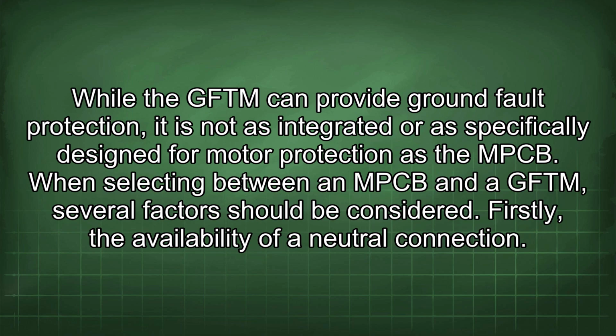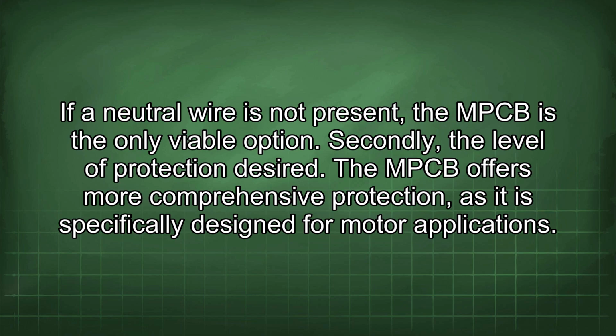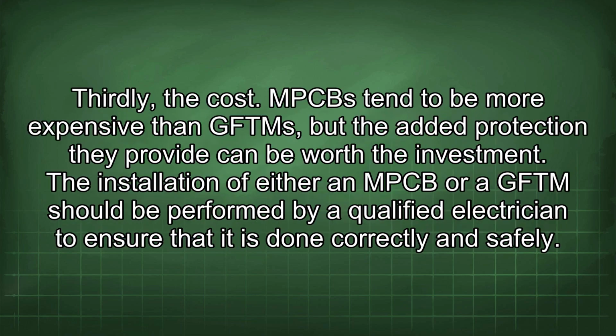When selecting between an MPCB and a GFTM, several factors should be considered. Firstly, the availability of a neutral connection. If a neutral wire is not present, the MPCB is the only viable option. Secondly, the level of protection desired. The MPCB offers more comprehensive protection, as it is specifically designed for motor applications. Thirdly, the cost. MPCBs tend to be more expensive than GFTMs, but the added protection they provide can be worth the investment.